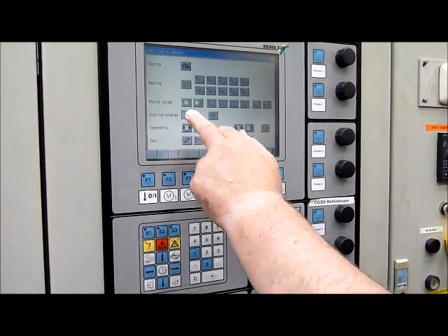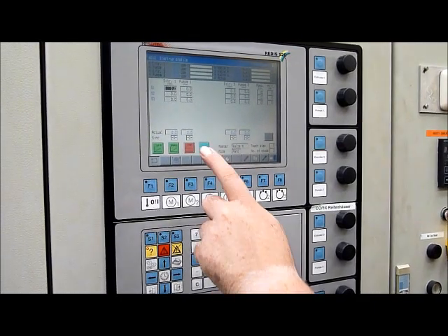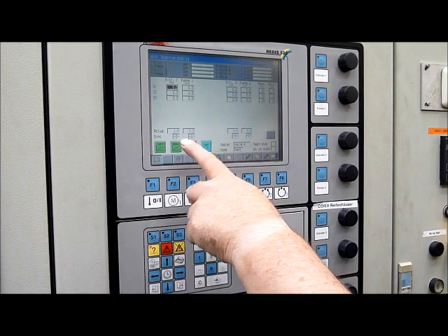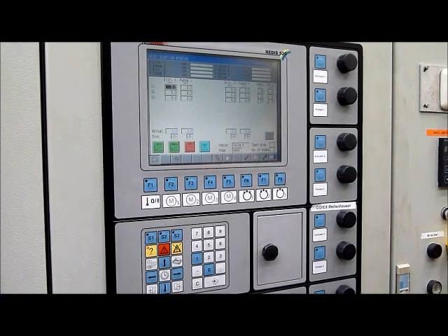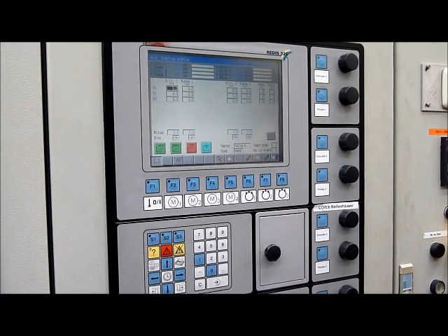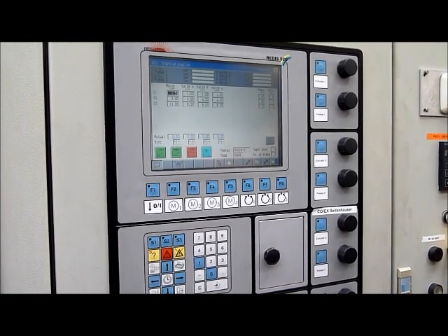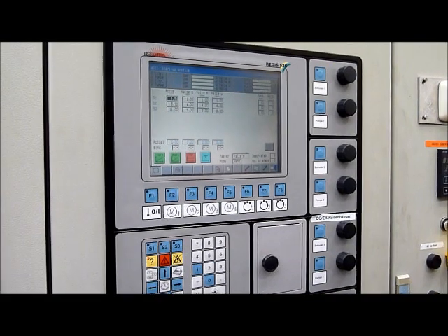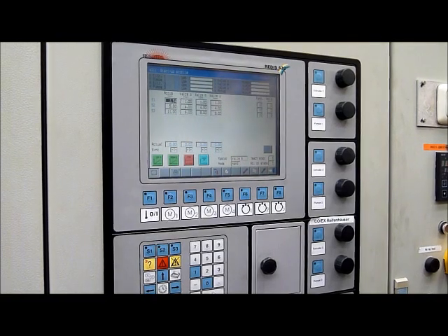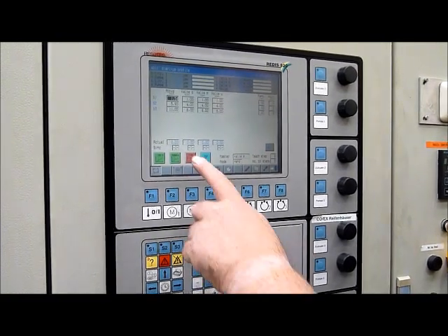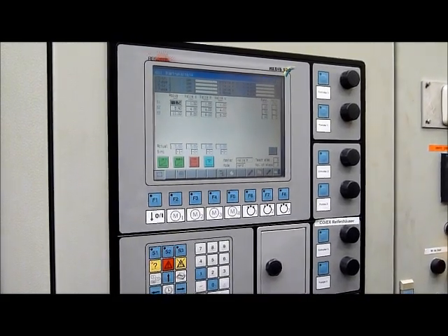The startup program is where all the auto connections are made. Generally you don't have auto on, synchronous auto on the extruder and the pump, because they will chase after pressures in their auto program. But what you might want is a synchronization of all the rolls. There are 3 profiles which are built already, but you can make your own profile. That there needs to be switched on, so that eventually when your profile's in you can synchronize them.